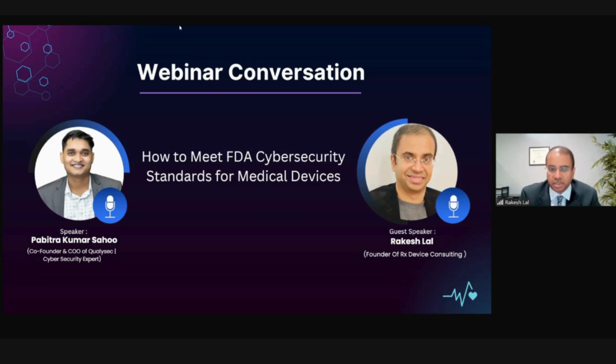It includes, among other things, the description of the device, the nature of the device, the risk classification of the device, various forms of testing data you may supply, performance testing, human factors testing, possibly clinical testing, and also the labeling and user materials that are supplied with the device, the user instructions, the device labels, and so forth.